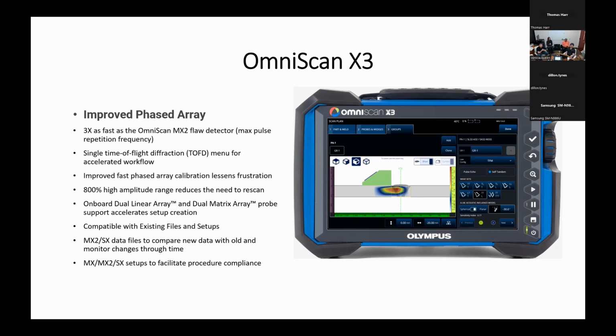Improved fast phased array calibration lessens frustration. It walks you through the scanning plan and calibration. Go step by step. Each menu kind of walks you through what you need to do, making it simple and fast. This unit also has 800% high amplitude range, which reduces the need to rescan. It also helps preserve some of that amplitude fidelity when you're transferring data from your machine to maybe a PC for evaluation. Has onboard DLA and DMA matrix array probe support, which accelerates setup creation.